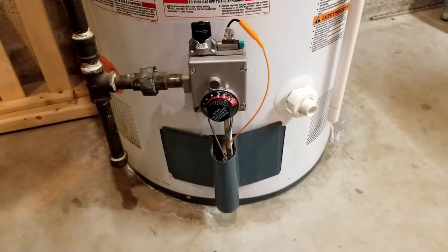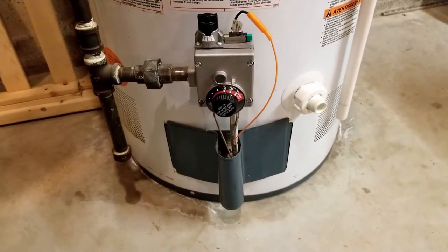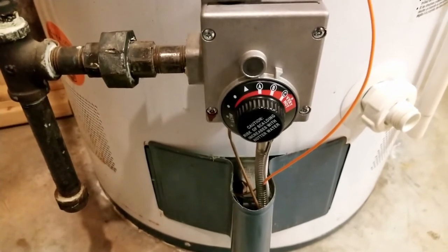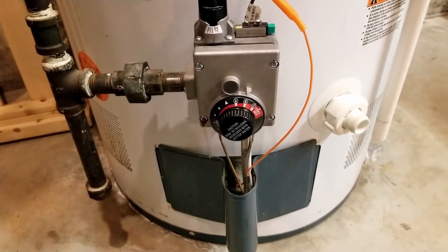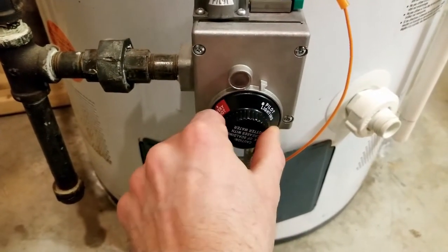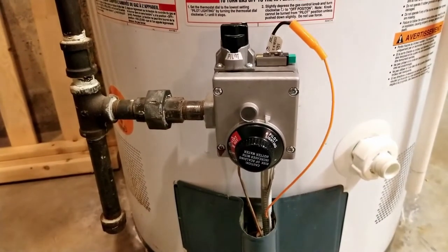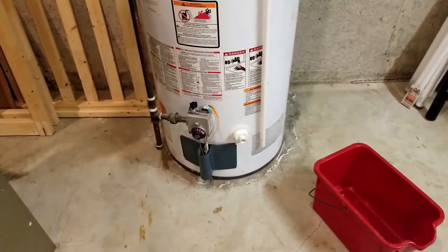Before you drain all the water out of your water heater, it is very important that you turn the burner down so the flame isn't going to kick on while the tank is empty — that could cause a lot of damage. Find the dial with the temperature adjustment and make a mental note of where your dial is before you turn it down, so once you're done you know what setting to return to. On mine I'm around B. Just turn it clockwise all the way past low, all the way to pilot lighting. Now the burner is not going to kick on, but it will keep the pilot light on so you don't have to relight it.